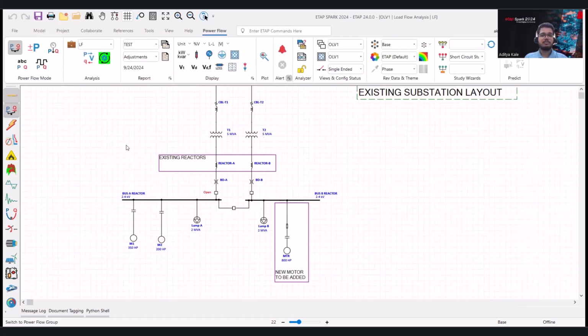Let's look at the load flow study. I'm going to start the study with a normal configuration. Here we have the motor bus voltage at 89%. Keep in mind this voltage drop is because of the losses and drop across the reactor. At 89% starting voltage, the motor can still be successfully started.